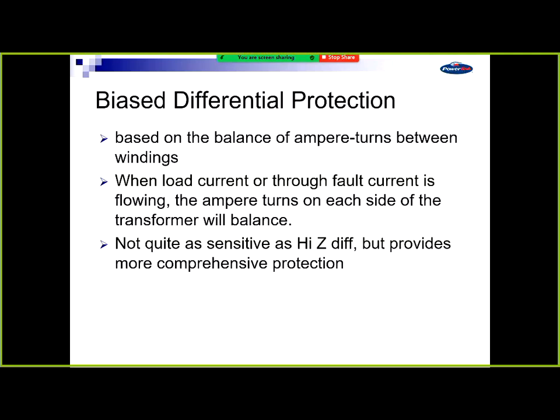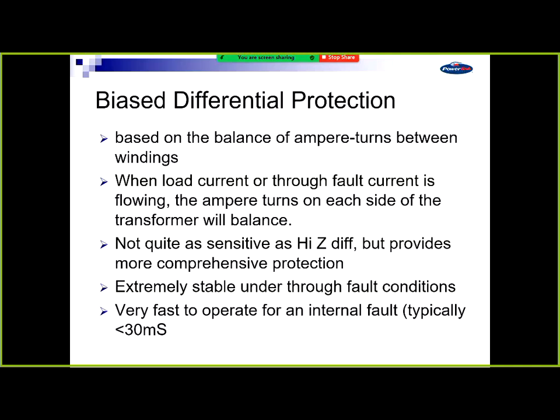It's not as sensitive as high impedance, but provides good overall comprehensive protection. With the modern bias diff relays now, you can share the CT core with other things if you need to. High impedance you can't, because by virtue you get high voltages through it, so it'll damage other types of relays. So you can't share high impedance circuits. That's a disadvantage for them. And they're very stable for external faults, and they're very fast to operate. It's written down there as 30 milliseconds, but the ones we're getting now are in the low 20 milliseconds.